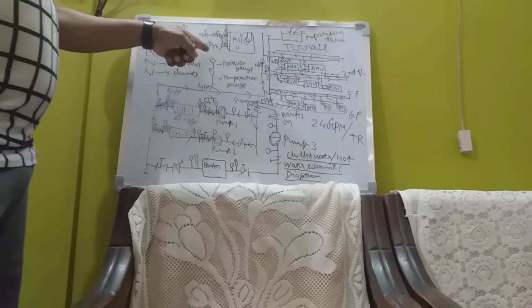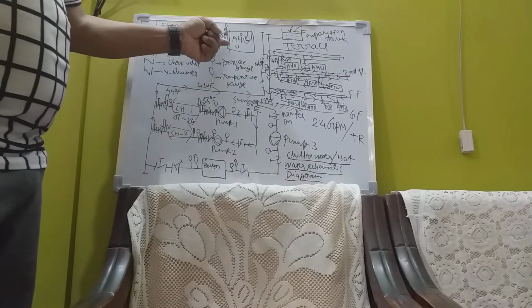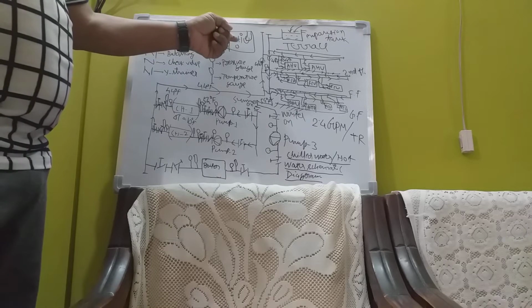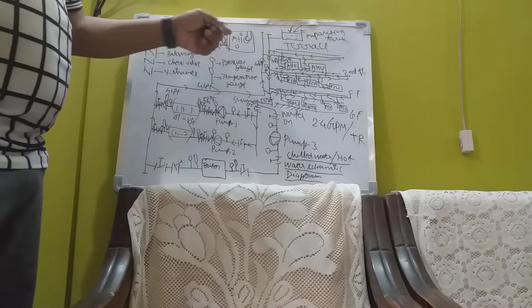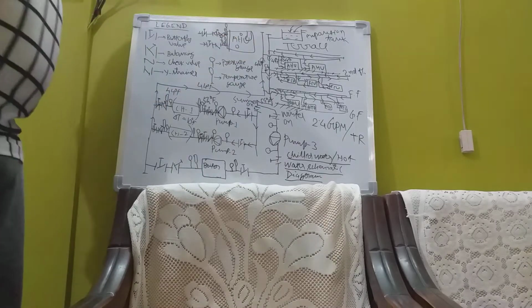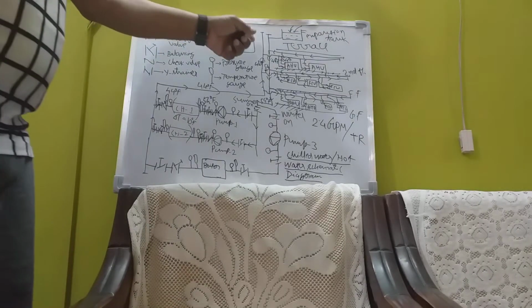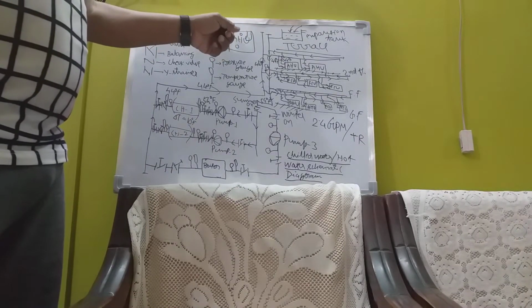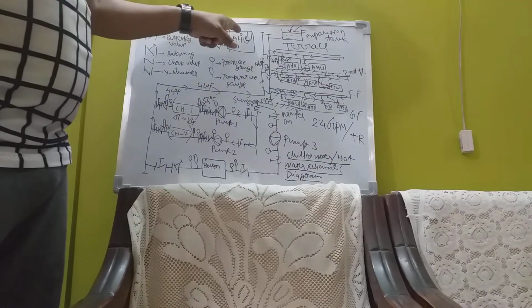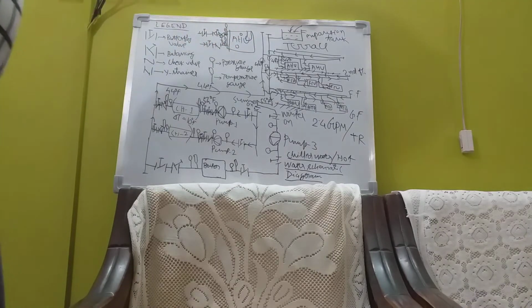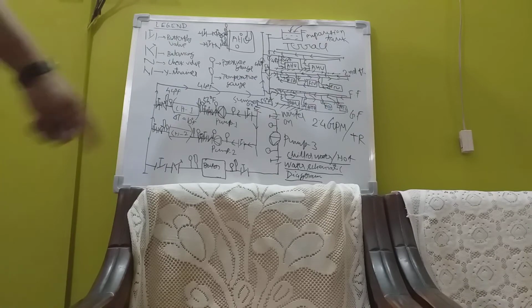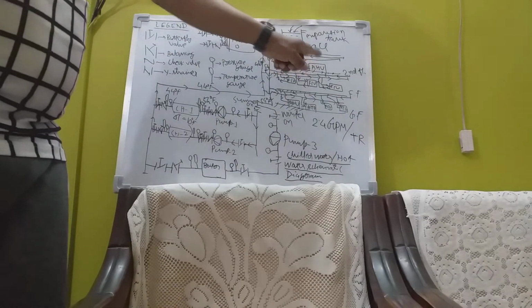In an air handling unit, we are putting the water inside the chilled water coil, going through it, and air is passing over the coil. So air is getting cooled. Water gets heated up, and hot water comes to the return pipe. That's what is happening in every AHU.